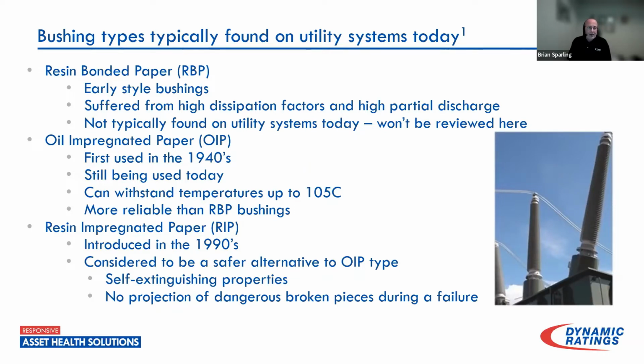One of the earlier styles, aside from wooden bushings from way back when, is one called resin bonded paper, RBP type bushings, that were fabricated long before the 40s and into the 30s at that time. These were paper insulated, but with a resin bonded paper. And the problem with these, they worked at the time, but over time, they've shown a propensity to suffer from high dissipation factors and partial discharge. Typically, you'll never find these on the systems today, so we're not going to talk about them today.